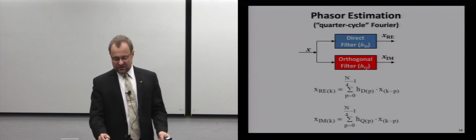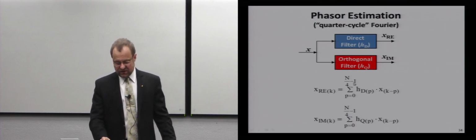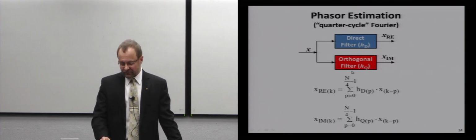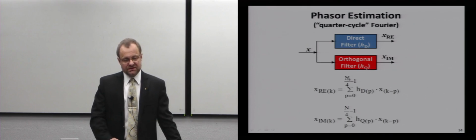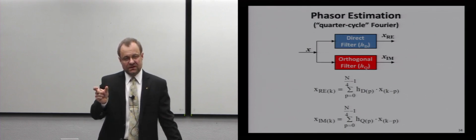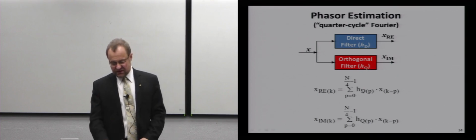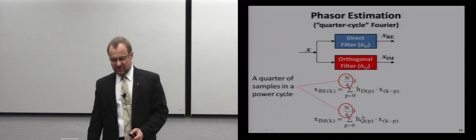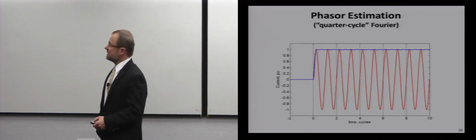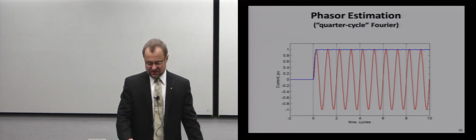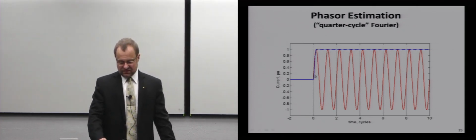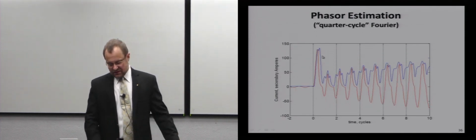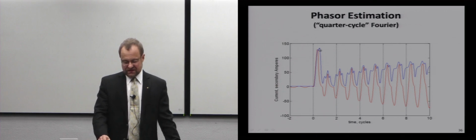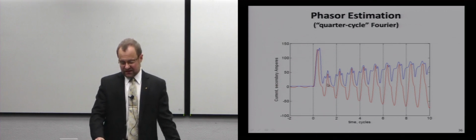So what I could do is I could apply longer data windows, meaning that I will watch that waveform for a longer time. And N here stands for the number of samples in a cycle. So N over 4 means that I am using quarter of a cycle window. So if the cycle is 16 milliseconds, I will use a window that is 4 milliseconds and do my best designing those filters to get the estimate. So now the ramp time is not instantaneous. It takes some time to really realize that the magnitude is not 0 but 1. And I have a slightly better performance. So here at least I don't overshoot by 100%. But again, this is not good.